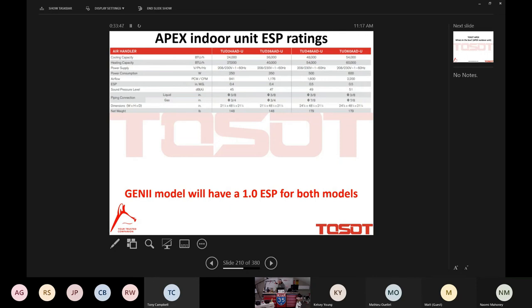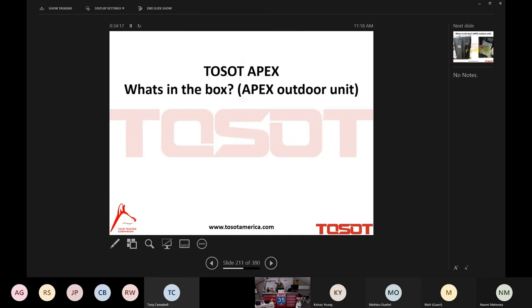So for those of you who have both in stock, that's okay, not a problem. But where you have a customer that points out to you right out of the gate that 0.4, 0.5 ain't going to cut it, well, there's your answer. You're in a unique situation to have both in stock. You're simply going to boost them up to the Gen 2 model, and away we go. And that will be true across the board for the four capacities, one inch of external static pressure.